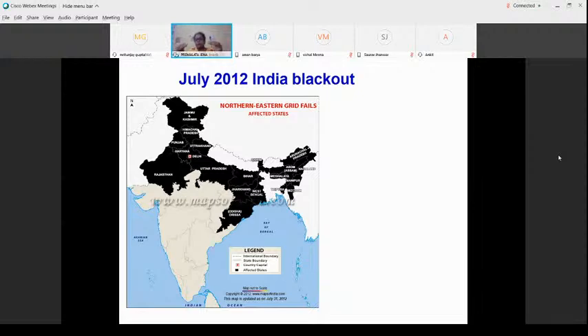And suddenly, what happened? Inside the northern side, some generating units had to be shut down because there was an imbalance between the generation and the load. If you do not stop or shut down the generators, there will be a problem in the stator and rotor windings. So therefore, there was a shutdown of the generators in the northern side. There is prime mover movement, but there is a loss of electrical energy, so there is an imbalance between mechanical and electrical energy. So suddenly you have to stop the generators, and a sudden generator shutdown means there is a blackout.